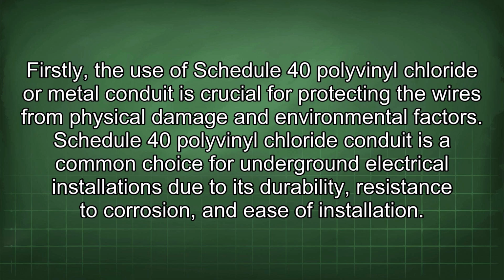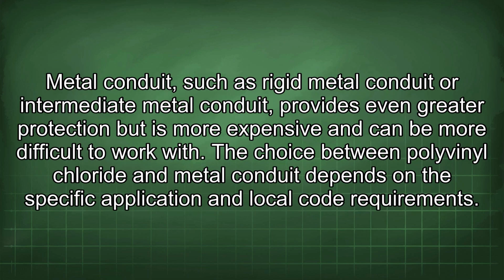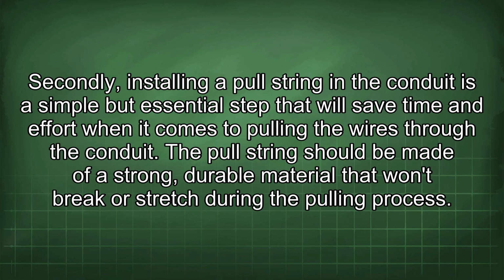resistance to corrosion, and ease of installation. Metal conduit, such as rigid metal conduit or intermediate metal conduit, provides even greater protection but is more expensive and can be more difficult to work with. The choice between polyvinyl chloride and metal conduit depends on the specific application and local code requirements. Secondly, installing a pull string in the conduit is a simple but essential step that will save time and effort when it comes to pulling the wires through the conduit.